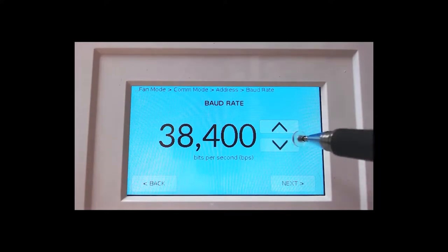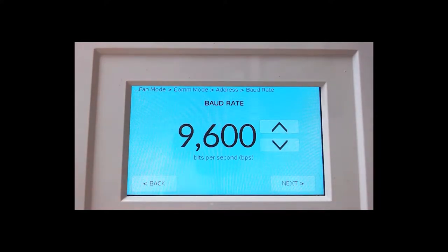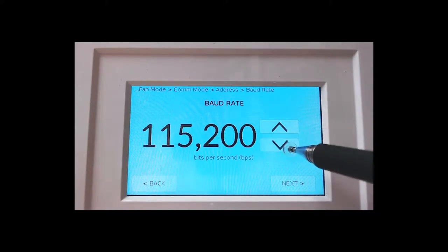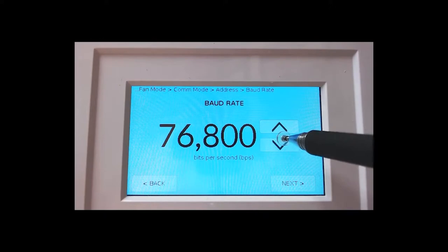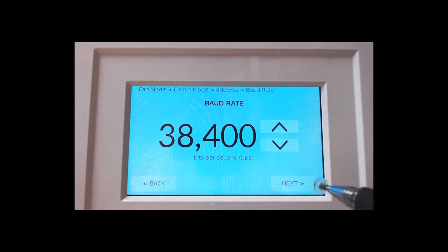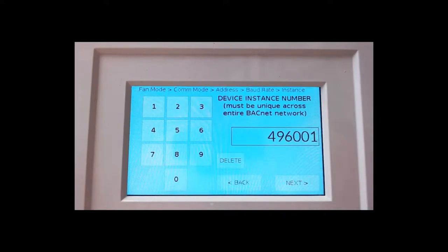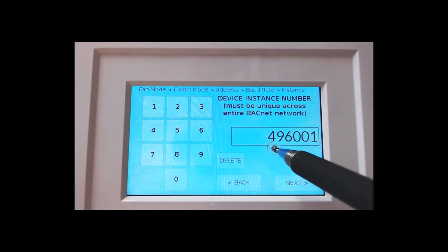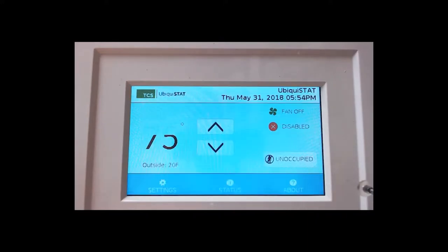Now, if I set this at TCS bus, I could go all the way down to 9600 because on the TCS bus, we only send change, so the network is a lot less active and a little more forgiving than it might be on BACnet. And we can set this as high as 115,200. So we'll go ahead and leave that at 38,400. And then this gives us a device number. What this does is just combine the BACnet manufacturing number that was assigned to us with the address that I just gave it. And that gets us right here into the main monitoring screen.